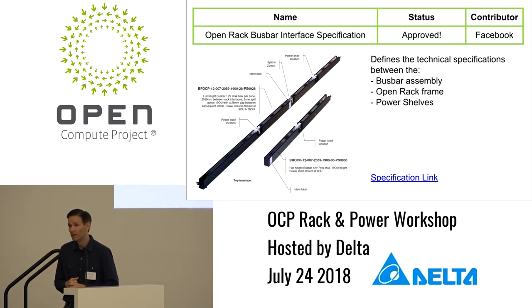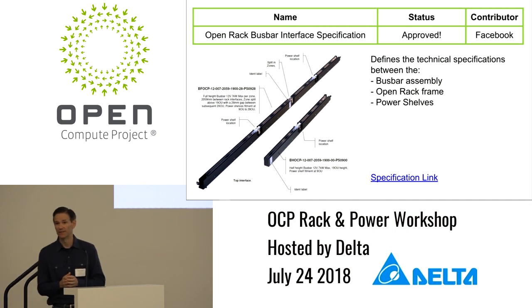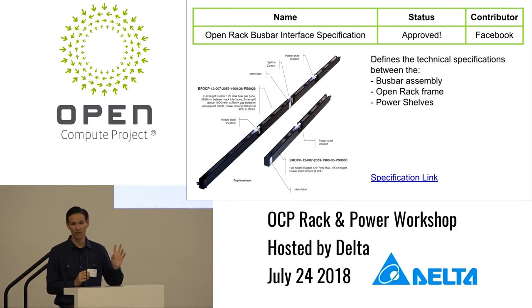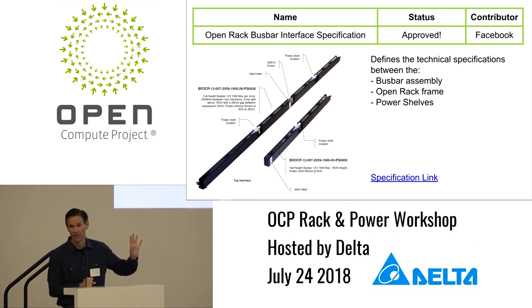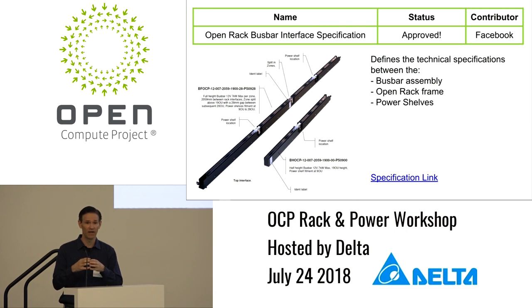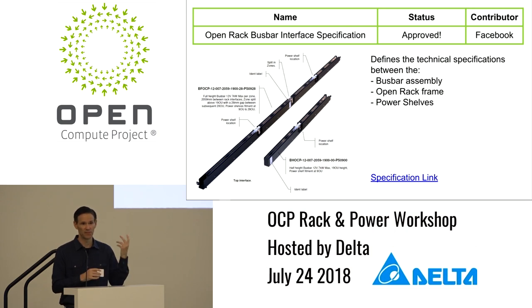Question: what are you doing for 48 volts? For the 48-volt, this particular specification covers both the 12-volt and the 48-volt bus bars. The picture shown is a 12-volt, but the volumetric for the bus bar is the same — the outer shell interface is the same whether it's 12-volt or 48-volt. So this specification allows both to comply.